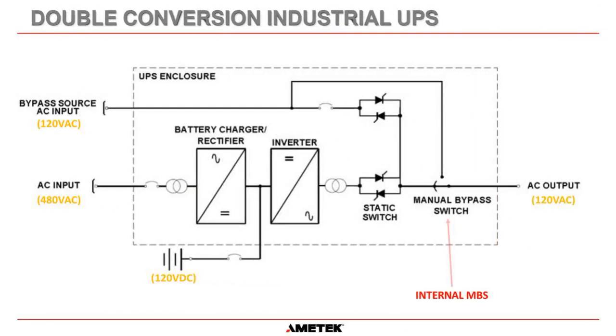So on the screen here, you'll see the basic single line drawing for one of our systems that has an internal MBS. And what do we mean by an internal MBS? Well, what we mean is the actual rotary bypass switch is on the UPS itself. It's usually on the front panel, and therefore the switch is integral to the UPS unit. Okay. That is what we call an internal MBS.